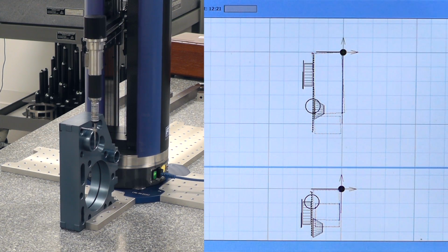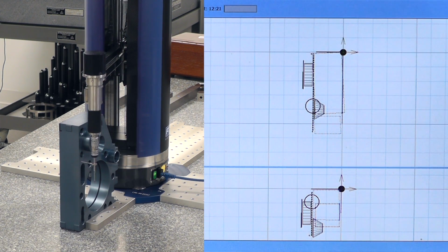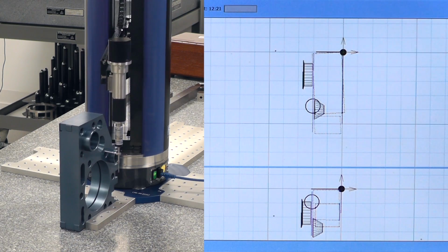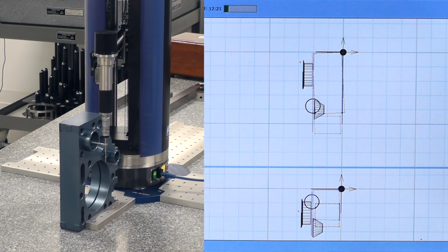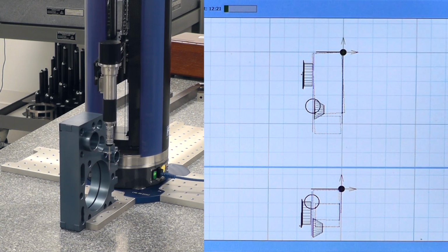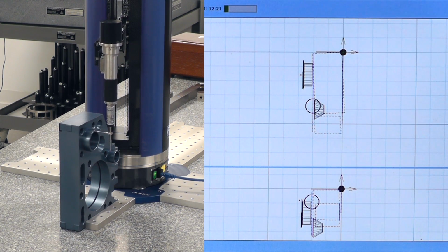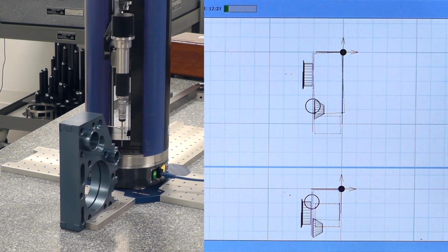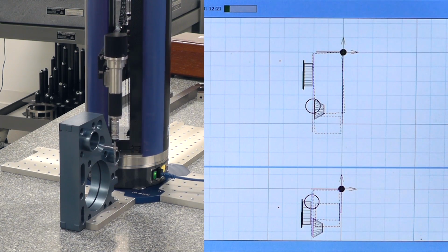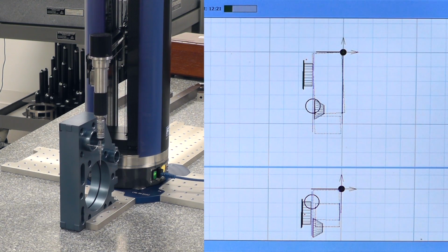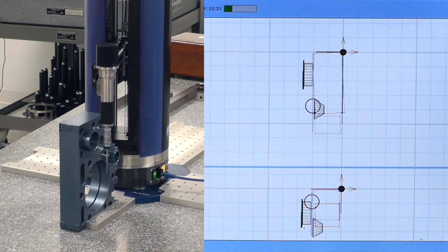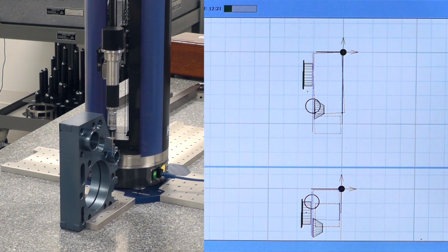the horizontal probe. Now it's measuring a plane, because when we're using the zCAT or any other CMM, when you start measuring diameters and cones and lines, it likes to reference off of a plane. So the first thing I do a lot of times is measure a plane so I can reference off that. Here I actually measured another plane on the top of that cylinder, and now I told it to measure the outside diameter of that cylinder. And again, we're using strictly the horizontal probe.